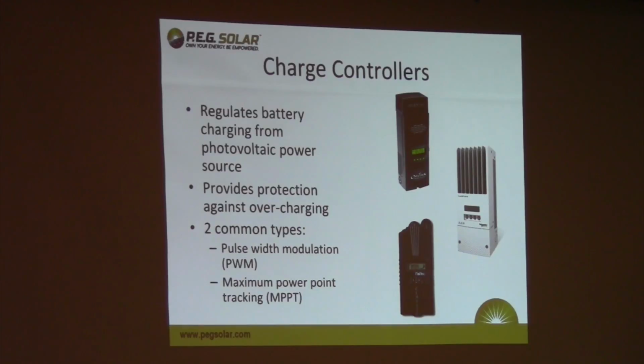Right, and you can typically program them for different types of batteries, depending on your battery chemistry. Take a typical flooded 12 volt battery: you're going to charge it at 14 and a half volts, then float or cut off at that point. An AGM battery, you might charge at a slightly lower voltage so you don't damage the glass mat inside. All that can be programmed into the controller. Typically you'll bulk charge up to a certain threshold, then hold constant voltage while the current tapers off so voltage never goes above that threshold, and then drop to a slightly lower floating voltage once you've completed the full charge cycle.